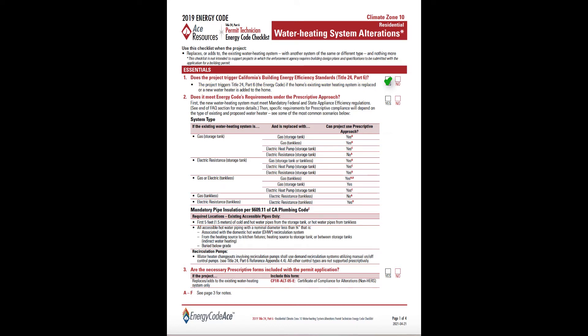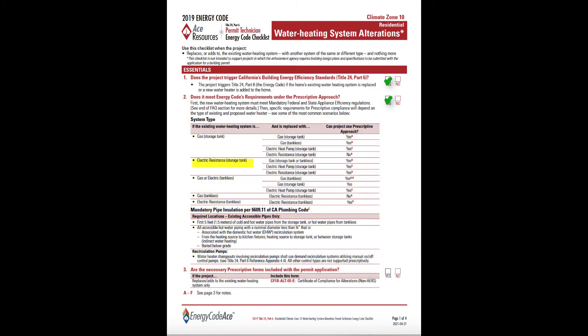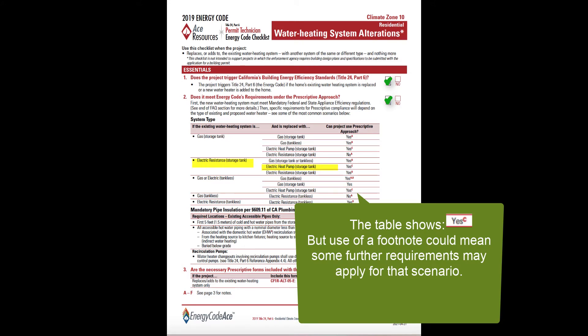The permit application indicates a change from an electric resistance storage tank water heater to an electric heat pump water heater. According to part 2 on this checklist page, can this type of project use the prescriptive approach? Yes — according to the table, a project that replaces an electric resistance storage tank with an electric heat pump water heater can use the prescriptive approach. Be aware, though, that a footnote is also cited for this scenario in the table, which likely means some additional requirements apply.